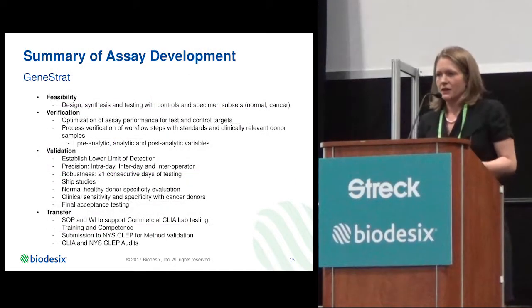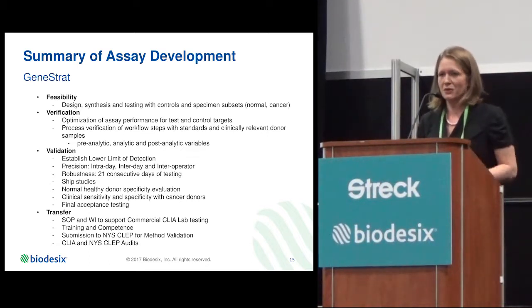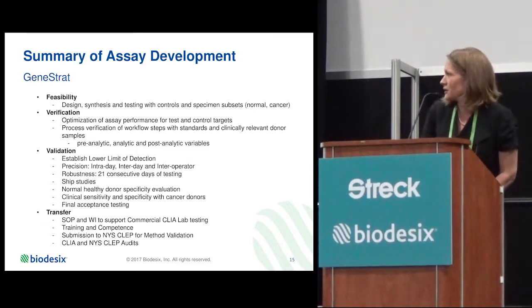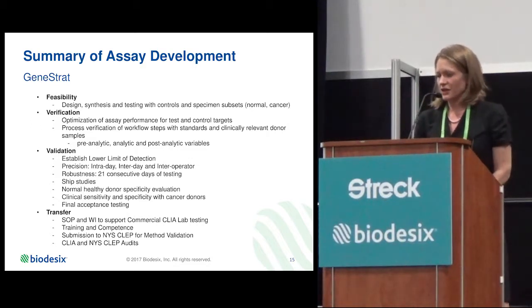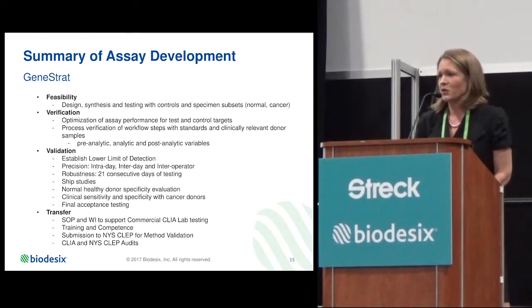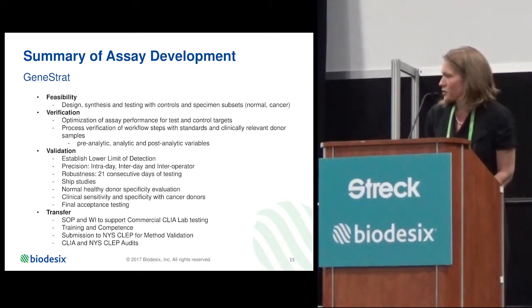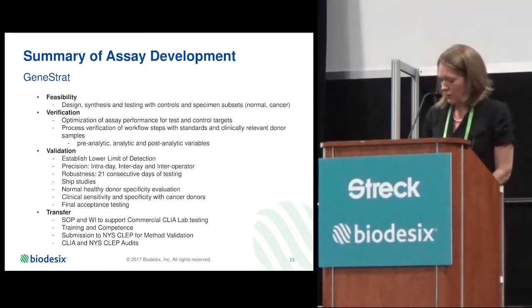At Biodesix, we follow a well-defined product development process that starts with feasibility — where we identify and design around those technologies — followed by a verification phase to optimize every single step in the workflow. We then lock the assay and perform a validation covering limit of detection, precision, accuracy, robustness studies, shipment stability, normal healthy donor studies, and clinical validation with reference samples known to be positive or negative. The final step is transferring to the CLIA laboratory and submitting to our quality and regulatory group.